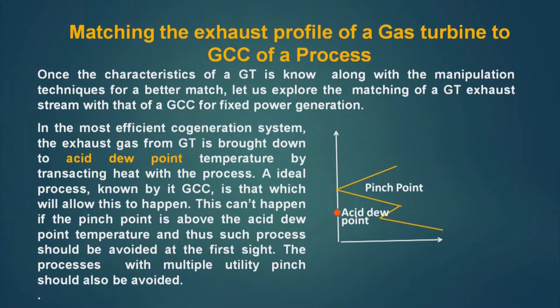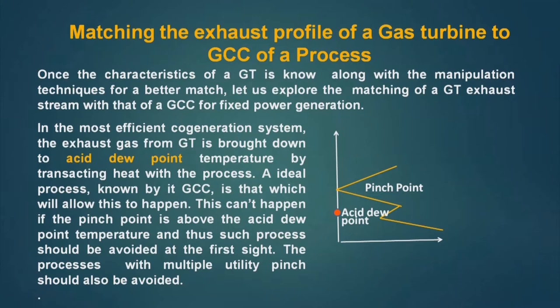Let us see when a co-generation system in which we are producing power and the hot gas from the gas turbine is also used as a hot utility. In such a co-generation system, how the hot gas from the GT can be used optimally. In most efficient co-generation systems, the exhaust gas from the GT is brought down to the acid dew point temperature by transacting heat with the process, because we cannot go below the acid dew point temperature — otherwise condensation of acid will take place in the gas phase and that will erode the equipment handling the gas.